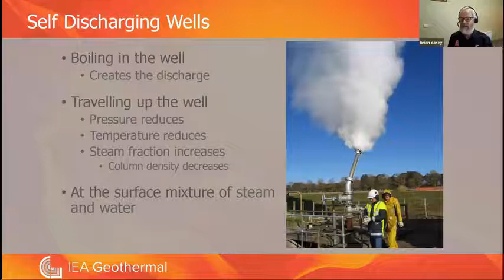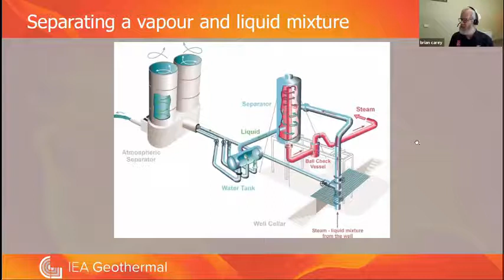Once you've got your two-phase fluid at the surface, you need to separate it into vapor and liquid. The two-phase mixture comes up the well and is introduced to a tall vertical vessel, with the fluid entering on the side, causing it to spin. The liquid, being denser than the steam, drops to the bottom of the vessel and is extracted there. The steam, being less dense, rises to the top and is extracted through a pipe running up through the vessel, shown here in red. So it's a simple separation process based on the density contrast between steam and water.